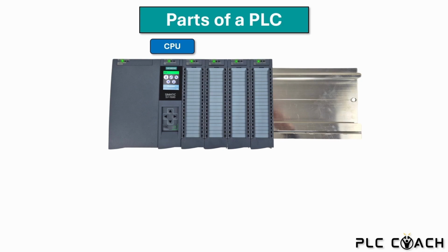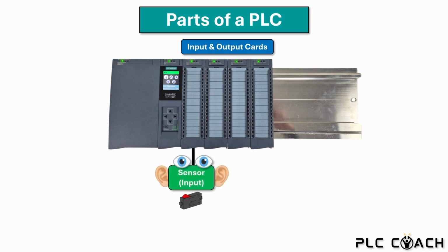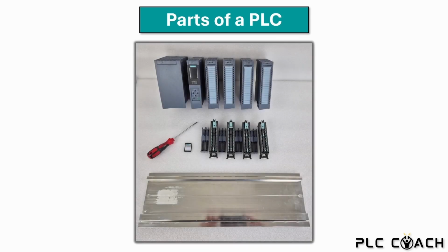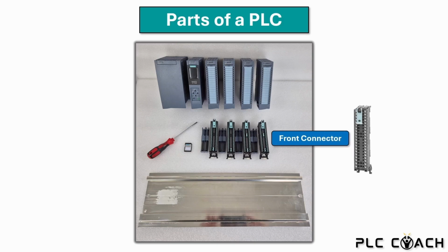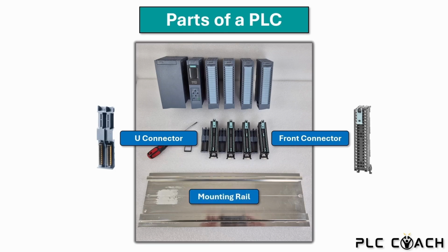The Simatic S7 1500 requires a memory card. With the S7-1200, this is optional. The next modules are input and output cards. Here we can connect our sensors and actuators. In this image you can see the components of our PLC. The so-called front connectors are used to connect the cables of the sensors and actuators with the input and output cards. The U connector establishes electrical and communication connections between the modules. All modules are mounted on a special rail.